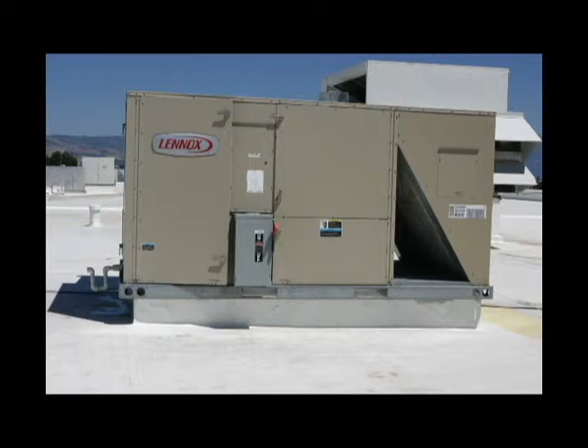In this box here, there's 2 air compressors, a cooling coil, and then the blower fan. And then on the roof, there's 2 condenser coils and the fans that keep those things cool. This unit by itself, in the event that we lose one compressor, won't actually keep the data center cool, so we added a second one last spring that's entirely on the roof. The only part of it you'll see in the room is the thermostat that's on the ceiling.